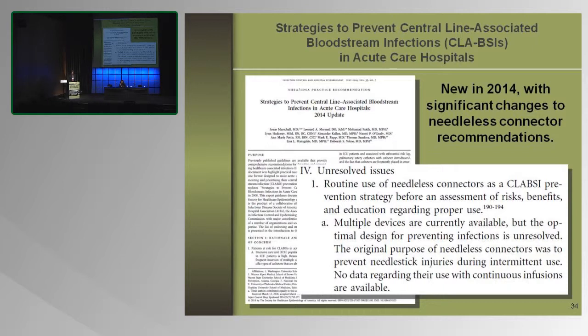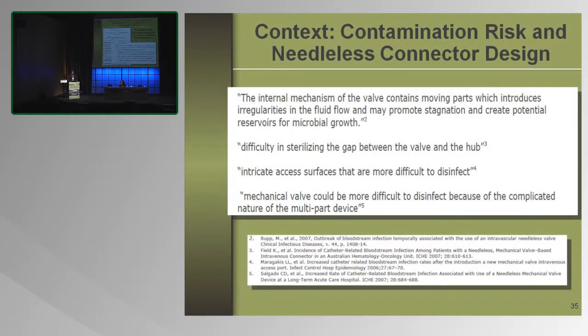And then they point out that the original purpose of these needleless connectors was for prevention of healthcare worker needle stick injuries and not prevention of infection in patients. And again, they comment on a number of the outbreaks that have occurred and point out the importance of the internal mechanism, the difficulty sterilizing gaps in the valves, the intricate access surfaces that are difficult to disinfect, and again, complicated, multiple moving parts.